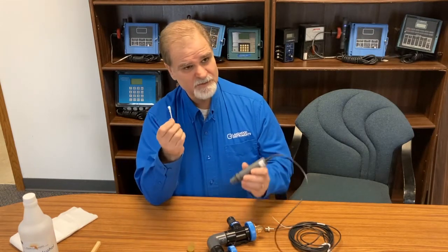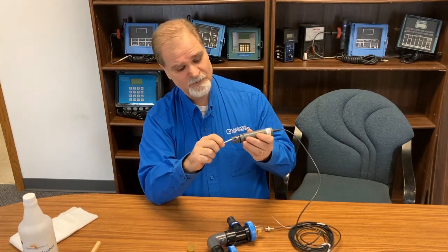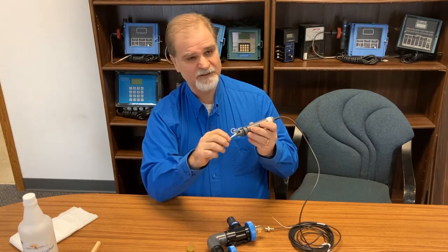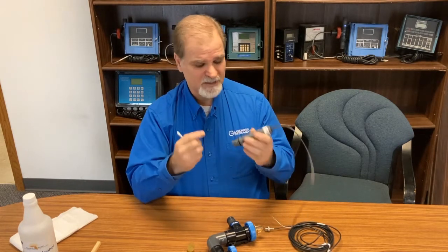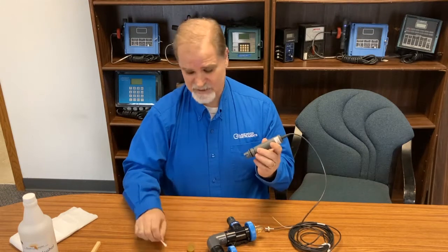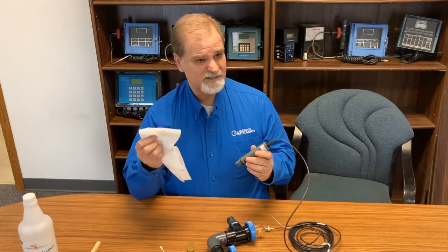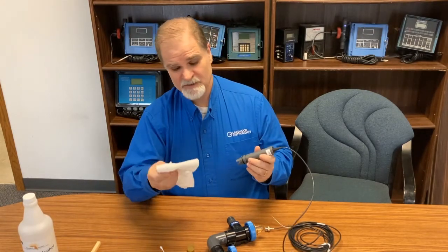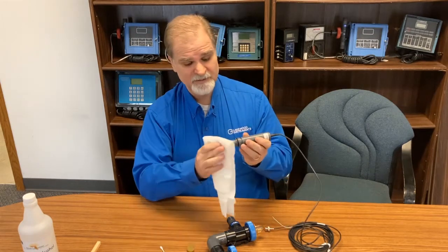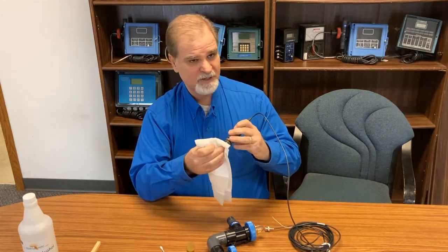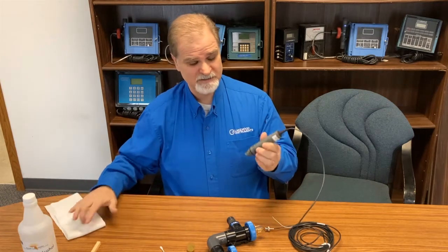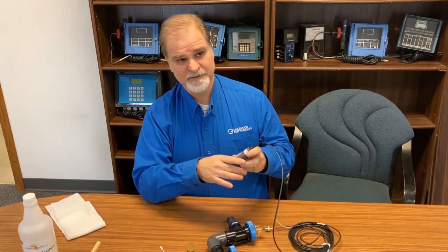You can also use a Q-tip to clean around the reference junction on the inside and around the glass itself. You want to use the minimum amount of scrubbing on that glass as possible. Do not use rags because rags inherently have oils. You can use a clean paper towel, but use a dabbing type motion instead of a rubbing motion on these. Again, so you don't scratch the glass. That's correct. Okay.